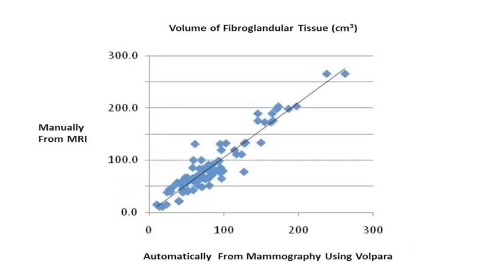Volpara was validated in several different ways. We have no absolute ground truth for breast density, so we have to compare the measurement of breast density with Volpara to other approaches, one of which was breast MRI. In breast MRI we can make images of the fat content and the water content of the breast; the water content is similar to what we think of as dense tissue in a mammogram.